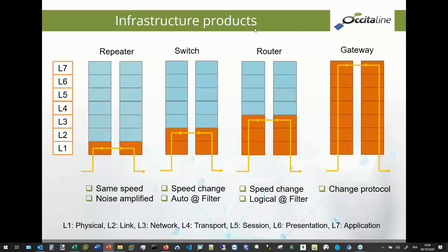The SCADA has one connection with the IP router. It sends to the IP router and asks one slave behind the router. This is a router. It's not the same as in other protocols. And a gateway often exists in BACnet or in other protocols. In this case, you split the vision of the field from the main network, often Ethernet, IP for 20 years.